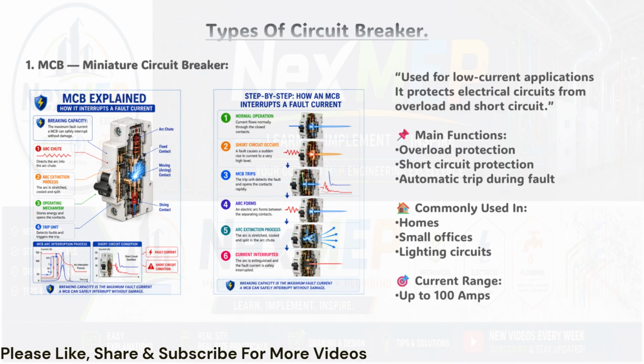When a fault occurs, the MCB's trip unit detects the abnormal current, opens the contacts rapidly, and an arc forms between them. This arc is then directed into the arc chute where it gets stretched, cooled, and split, safely extinguishing it and interrupting the fault current. Key thing to remember: MCBs are rated up to 100 amps. They don't protect against earth leakage or electric shock, that's the job of RCCB. But for basic circuit protection in homes and small installations, the MCB is your go-to device.